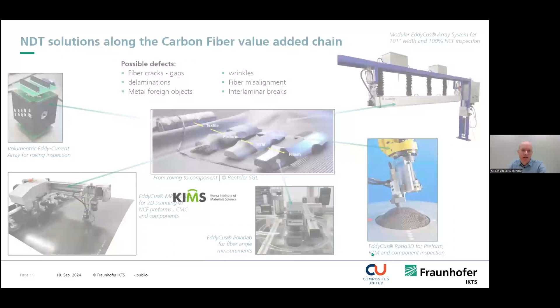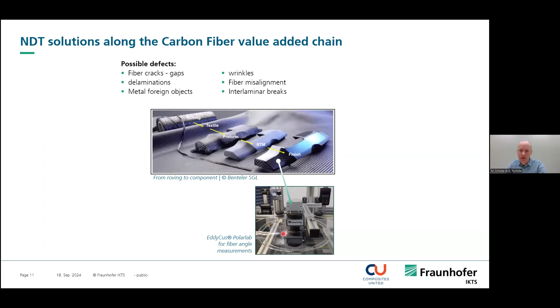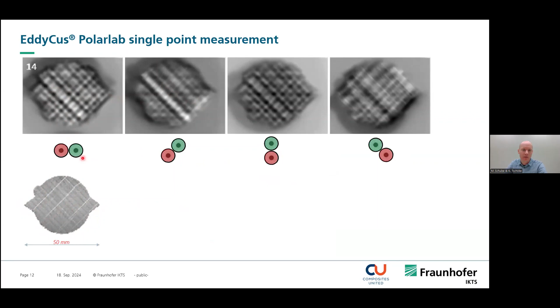To analyze small parts only for their angle or layer orientation, we have this so-called EddyCus Polarlab. It was also developed for BMW, so they had the task to monitor the fiber orientation in these small specimens. Here we see eddy current C-scans acquired with different probe orientations. You see that there is a different behavior in the C-scan when we rotate the probe. And this is the device. And we wanted to eliminate the cost-intensive computer tomography-based inspection of this type of specimen with this device.